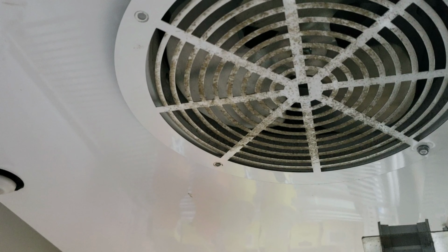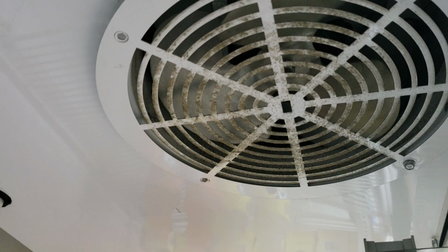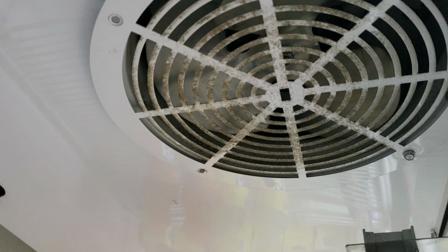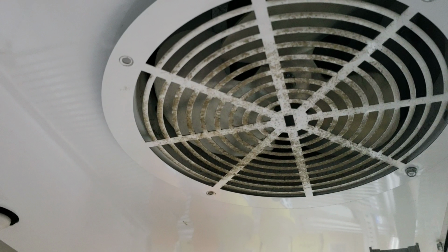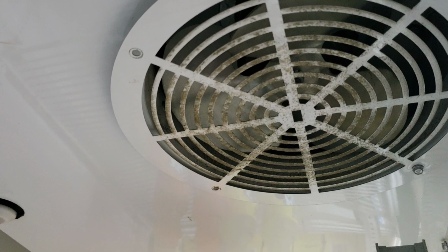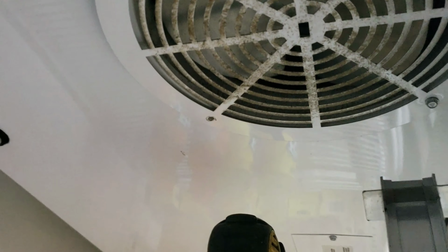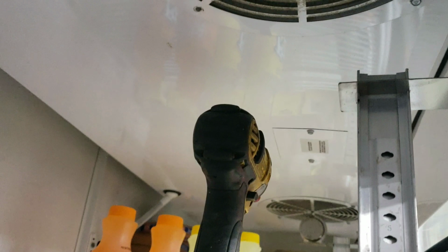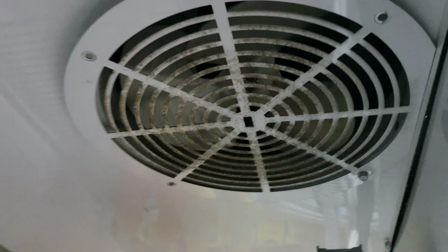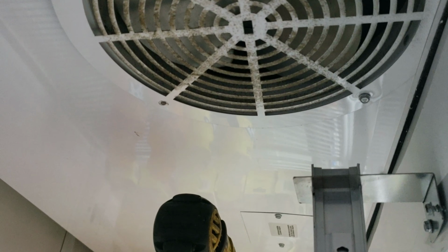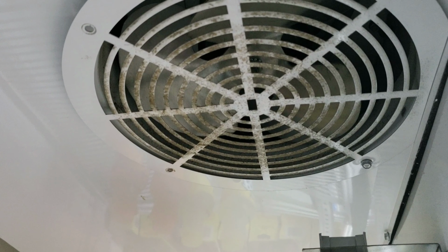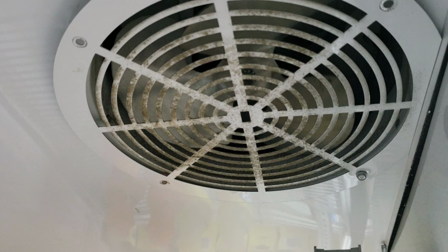Inspected the unit, had a clean condenser coil. The box was somewhat cooling, but then I noticed this fan here was doing a weird little number. It was almost like it was spinning backwards, which this is a 2-fan setup here on this evaporator. So we're gonna go ahead and get this fan pulled out and replaced.